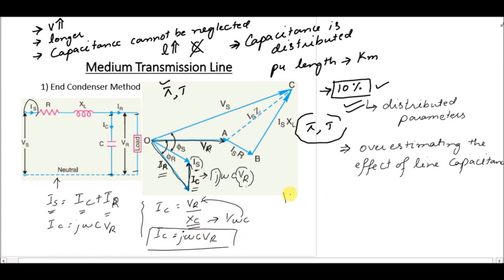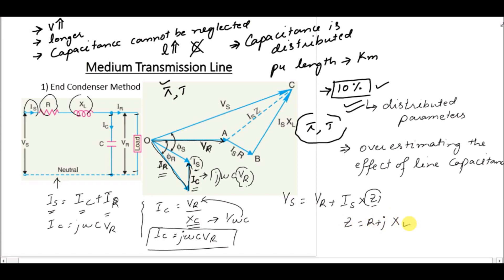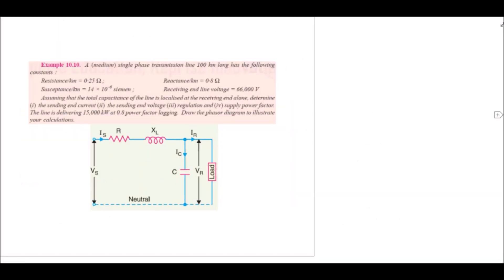To calculate the sending end current, IS = IC + IR. The sending end voltage is VS = VR + IS × Z, where the line impedance Z = R + j·XL. This is the brief discussion about the end condenser method of representing a medium transmission line.